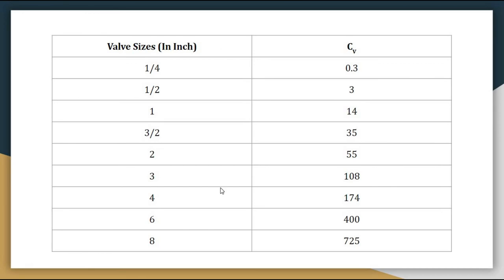The valve size is in inches on the left hand side of the table. From this table, if the valve size is one-fourth inch, then its valve coefficient Cv is 0.3, and vice versa — if the valve coefficient is 0.3, we can know that its size is one-fourth inch. Similarly, if the Cv is 108, then its size is 3 inch — a 3 inch valve has a Cv of 108. This table gives you a comparison between the valve size and its Cv coefficient.